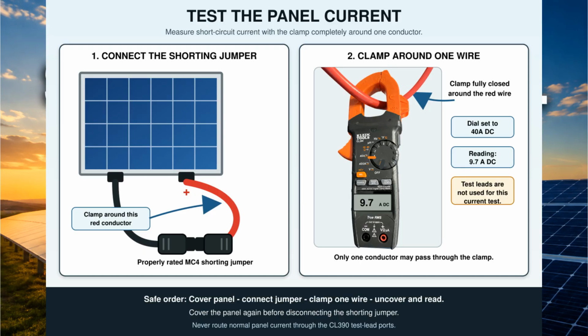Close the clamp completely around one wire in the shorting loop. Only one conductor can pass through the clamp. If both wires are inside the clamp, their magnetic fields can cancel each other. The meter may show little or no current, even though current is flowing. Uncover the panel and aim it toward direct sunlight. Our panel is rated at 10.5 amps ISC, and the meter shows 9.7 amps DC. The panel is producing current.